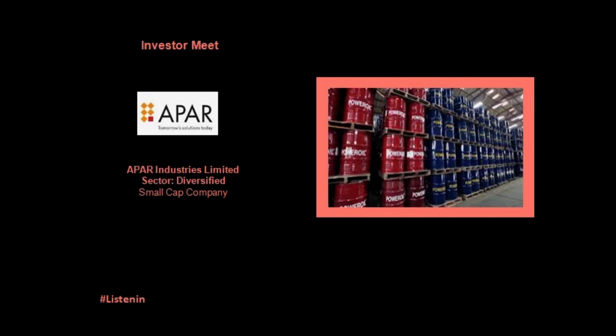To give you some insight into what's special about transformer oil, here's a power transformer. These are massive structures, sometimes about a quarter the size of this room, holding a few kiloliters of oil, sometimes 20 to 30 kiloliters. The oil acts as a coolant and insulant to keep the transformer cool, and it's also used as a diagnostic tool. Like in a human body, you take a blood sample to check a person's health. Similarly, you take a sample of the transformer oil to study the health of the transformer, since these are huge machines connected to the grid that can't simply be turned off and on.